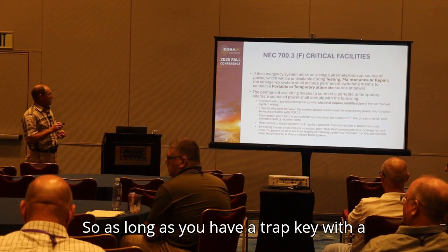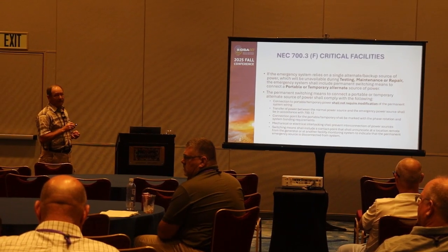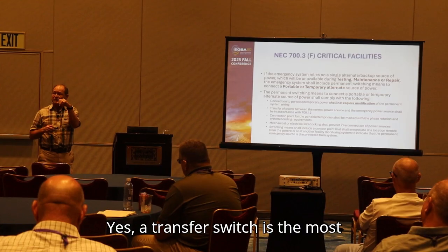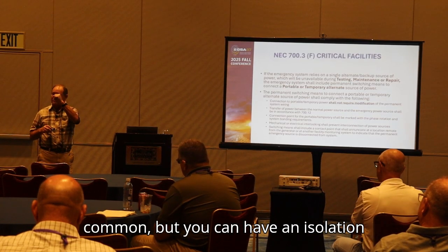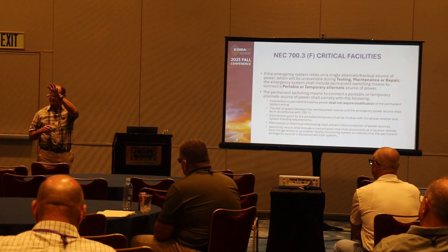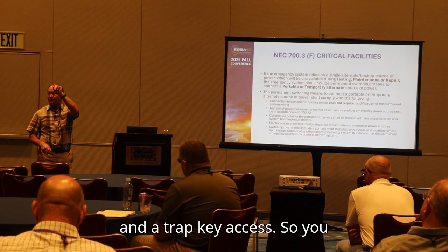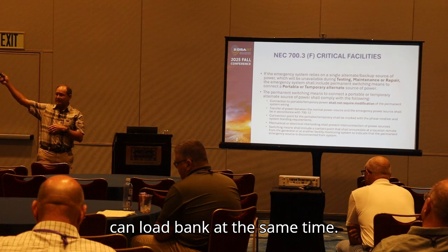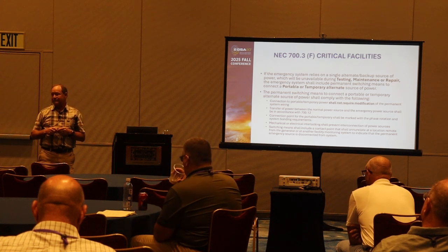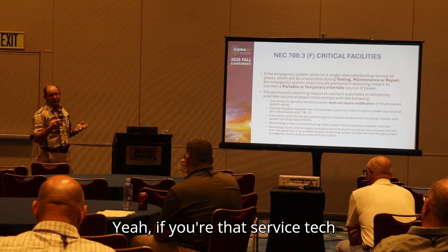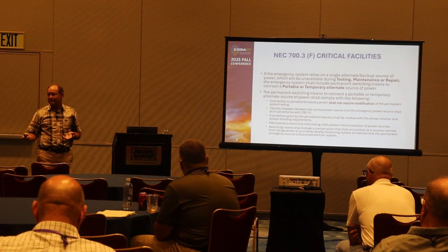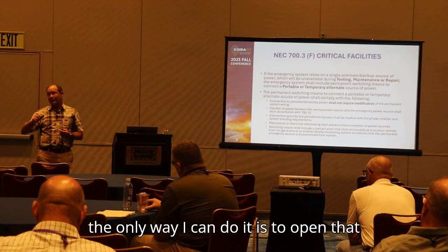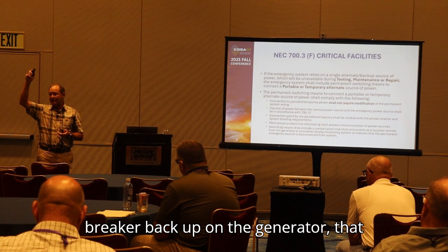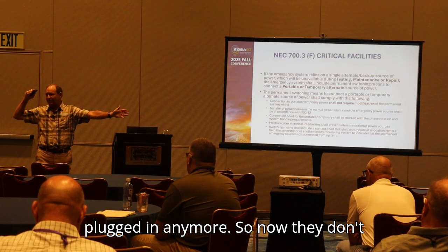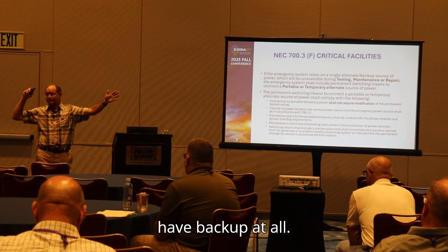So as long as you have a trap key with a breaker in your device. Yes. A transfer switch is the most common, but you can have an isolation switch in the cabinet and a trap key access, so you can load bank at the same time. If you're that service tech and I've got to load bank the generator, the only way I can do it is to open that breaker back up on the generator. That means I can't have a portable generator plugged in anymore. So now they don't have backup at all.